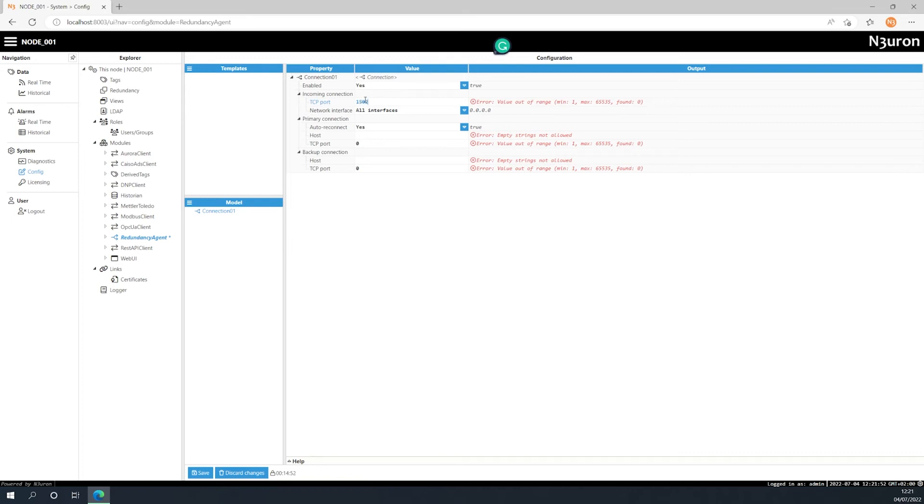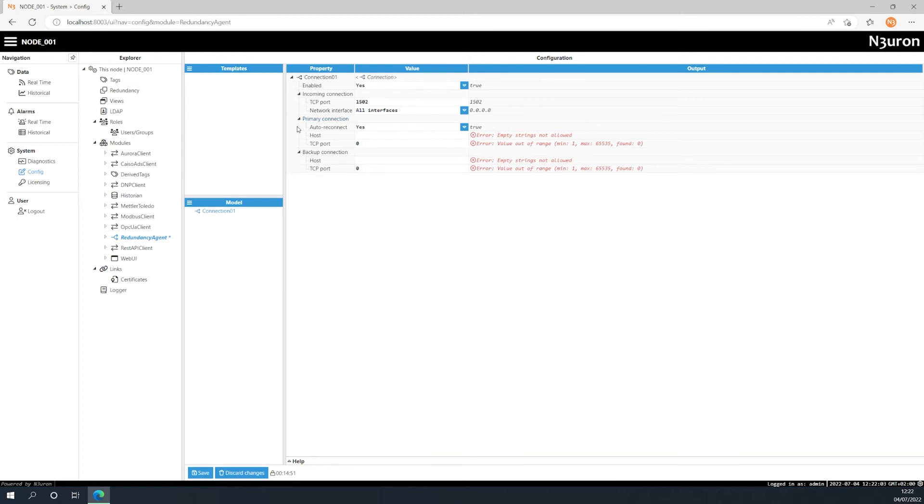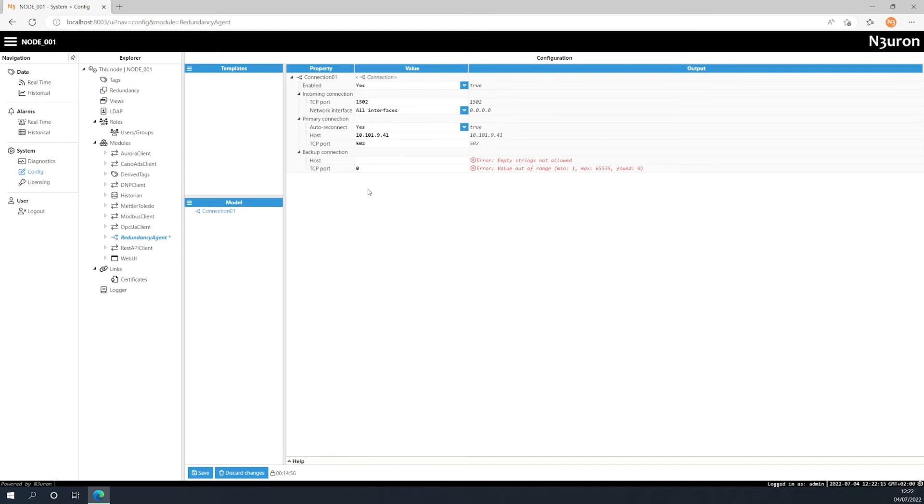First let's configure the TCP port that the redundancy agent will listen to. Then we can also specify which network interfaces will be accepting connections. In the primary connection we should enter the information related to the primary device or server. In this case we have entered the following IP for the host field and 502 for the port. The auto reconnect parameter is fine to leave with its default value since we want the connection to return to the primary device providing it is up and running after a disconnection.